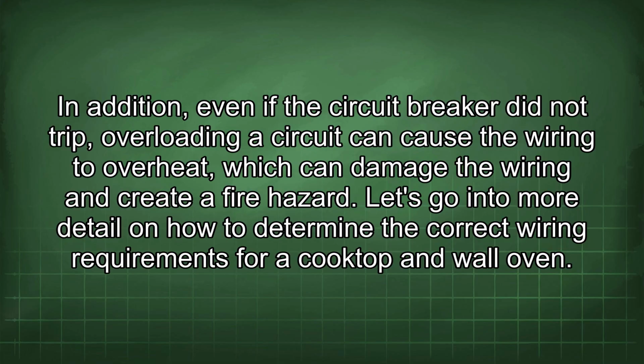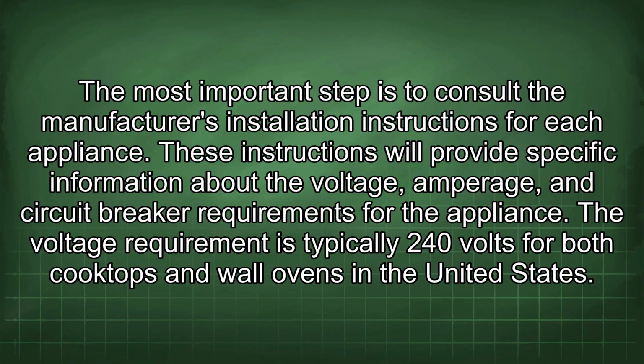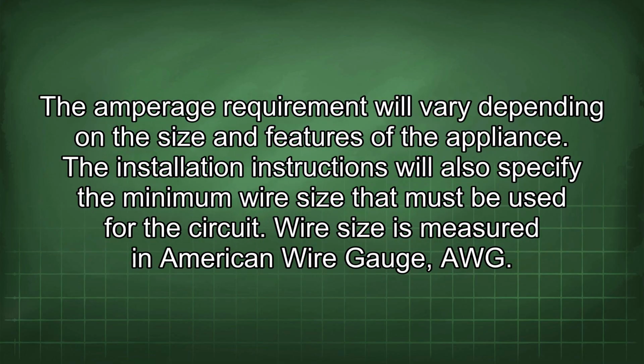Let's go into more detail on how to determine the correct wiring requirements for a cooktop and wall oven. The most important step is to consult the manufacturer's installation instructions for each appliance. These instructions will provide specific information about the voltage, amperage, and circuit breaker requirements for the appliance. The voltage requirement is typically 240 volts for both cooktops and wall ovens in the United States. The amperage requirement will vary depending on the size and features of the appliance. The installation instructions will also specify the minimum wire size that must be used for the circuit.